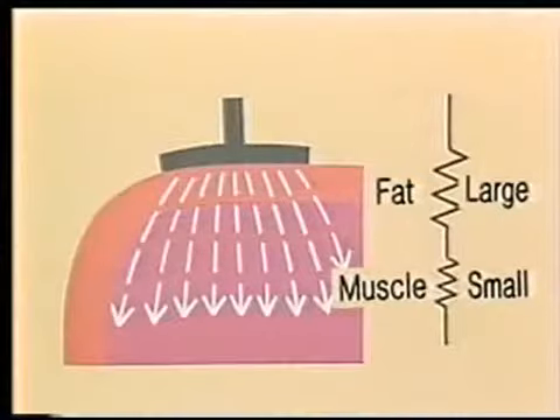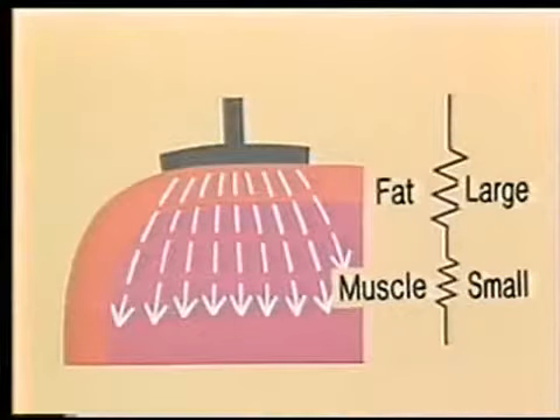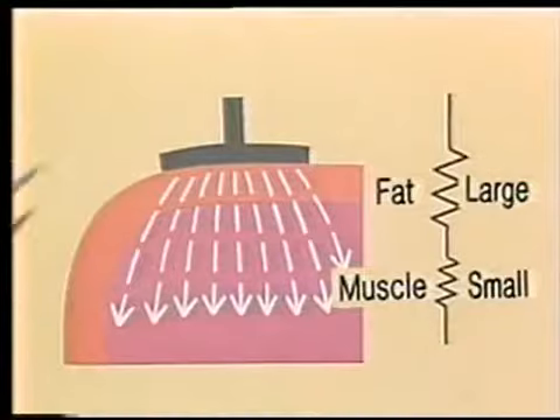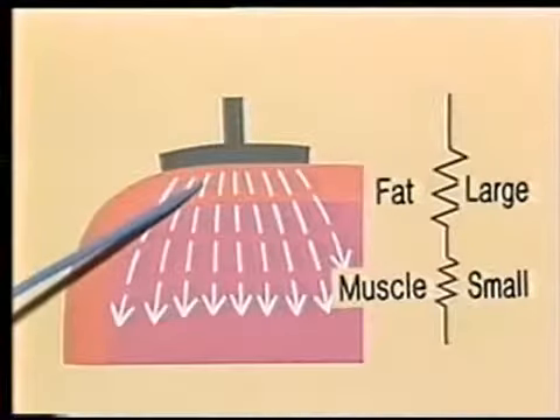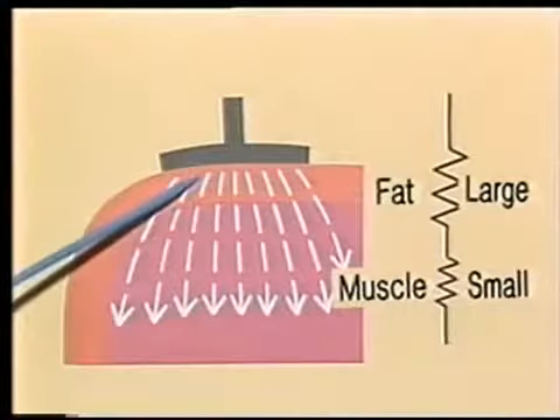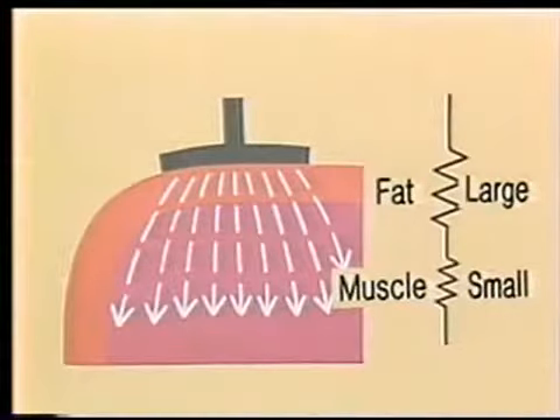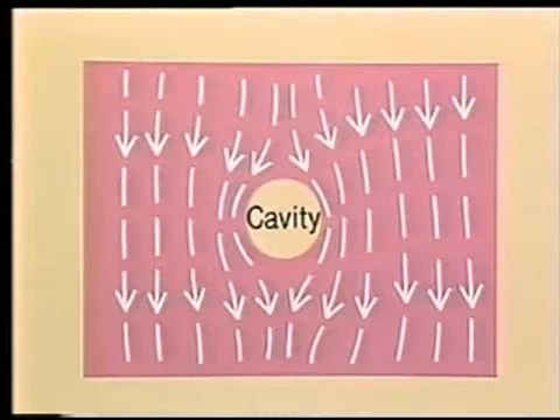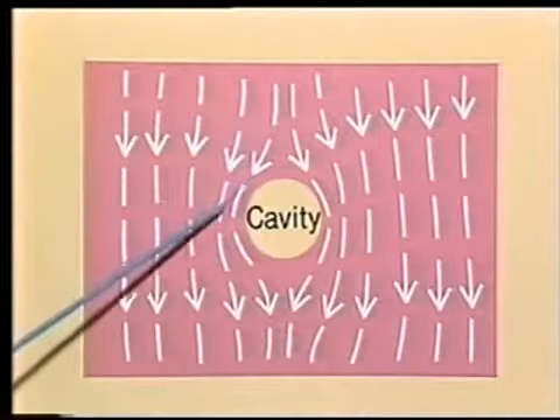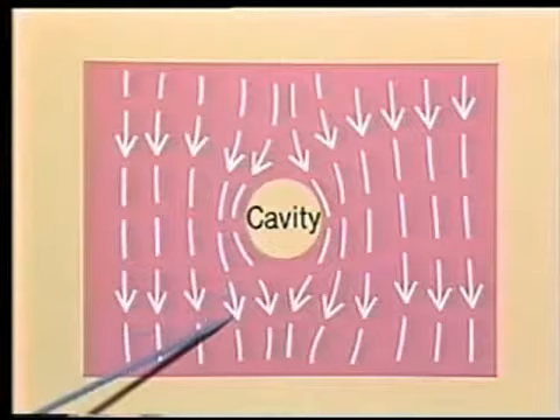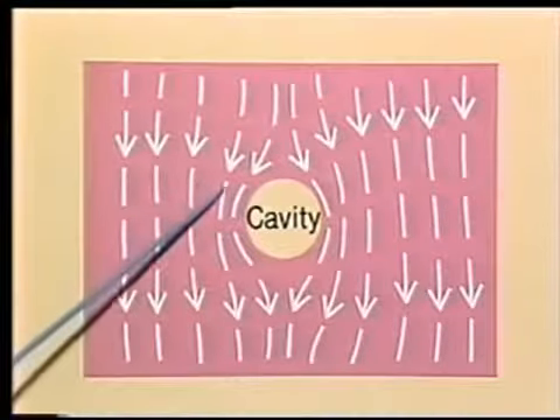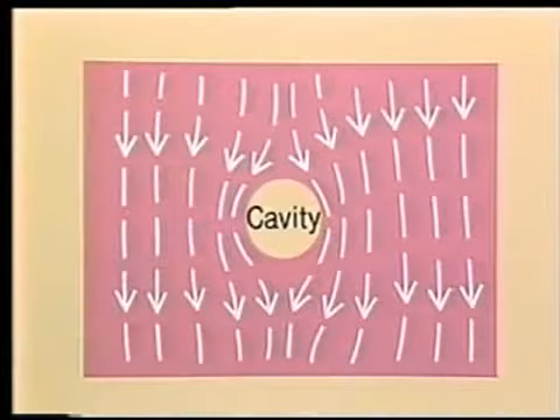It is very important to cool the surface of the body during heating. Just under the electrode is a layer of subcutaneous fat, under which is a layer of muscle. As fat has high electrical resistance, it generates more heat when an electric current flows through it. Moreover, the lines of electric force are fairly concentrated near the electrode, where more heat is generated. When air is in a body cavity, as shown in the illustration, the electric current is pushed aside to produce an area where the lines of electric force are concentrated, that is, where more heat is generated. This effect should also be noted.